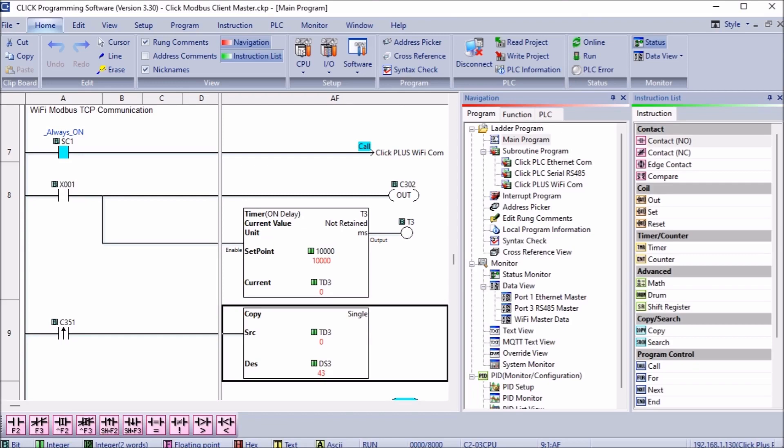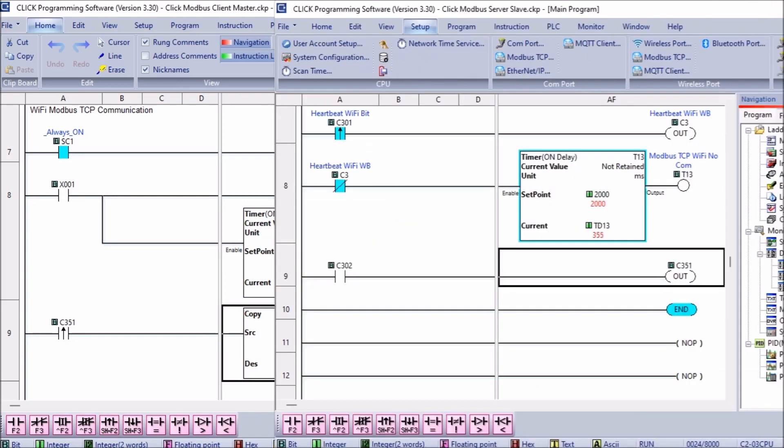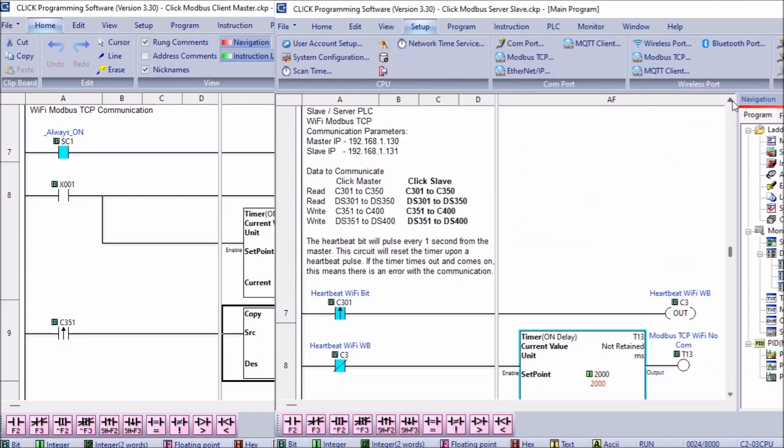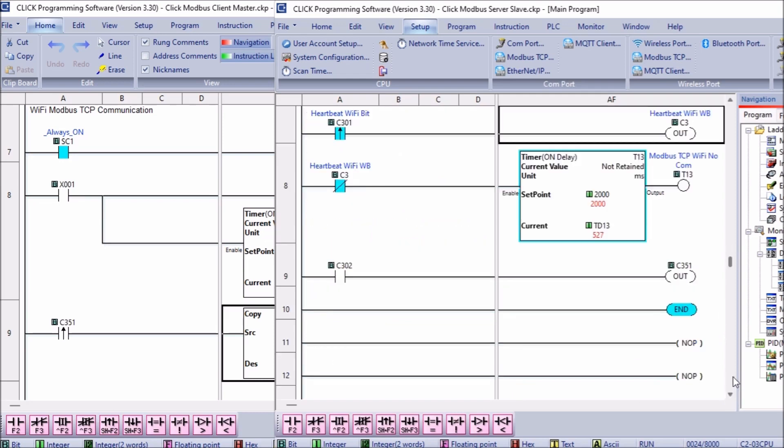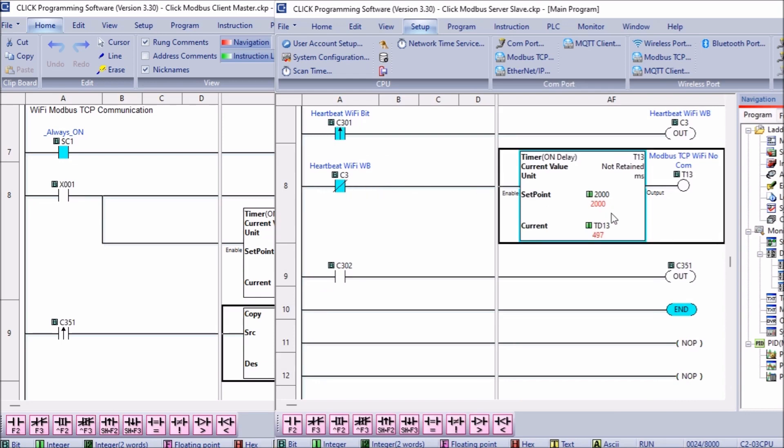The click server PLC does not need any code for communication to the client, other than a heartbeat to ensure the transmission is valid. This is an asynchronous communication from the client. The heartbeat pulse comes from the client bit C301. Using the leading edge of this bit to turn on an internal bit, we use this normally closed internal bit as the condition for a timer. If the timer times out and the timer done bit comes on, we know communications has been lost. This could be used later on in your program.